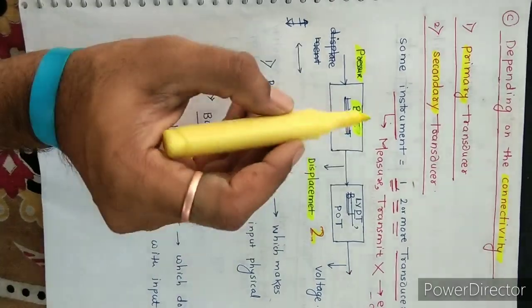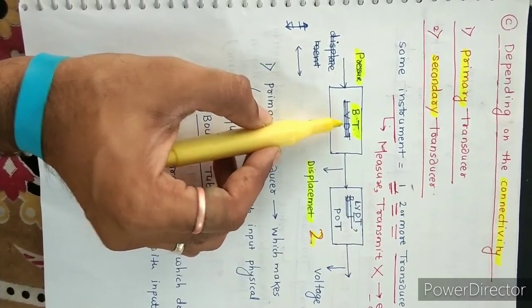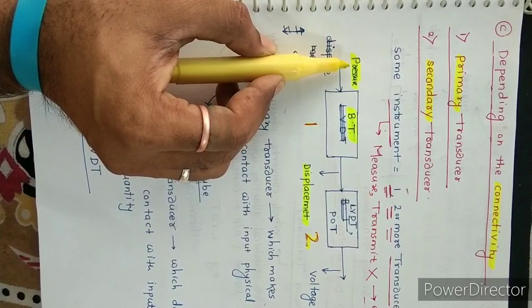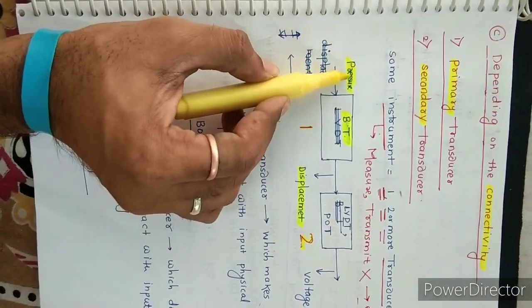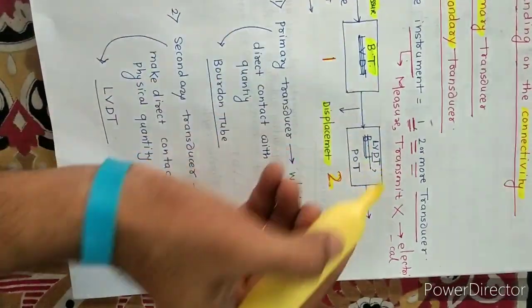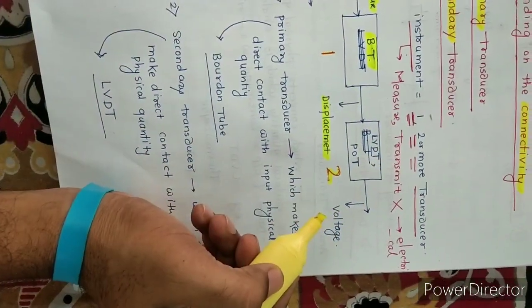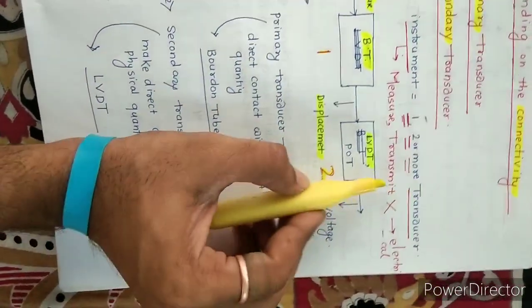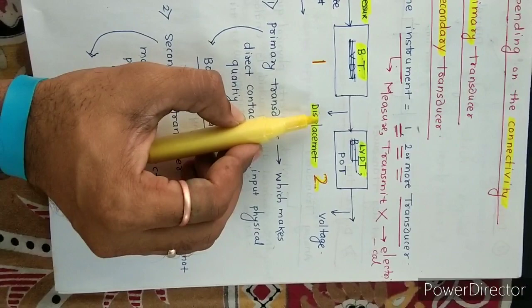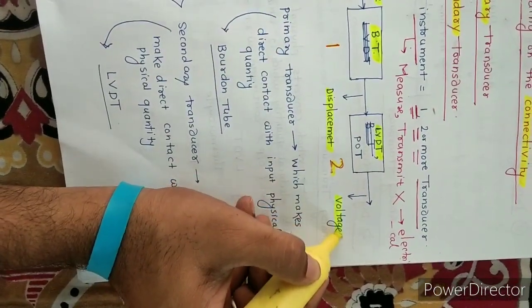Pressure is converted into displacement with the help of the Bourdon tube. The Bourdon tube is a mechanical transducer which converts one type of physical quantity into another type of physical quantity. Then the LVDT converts the displacement into voltage.